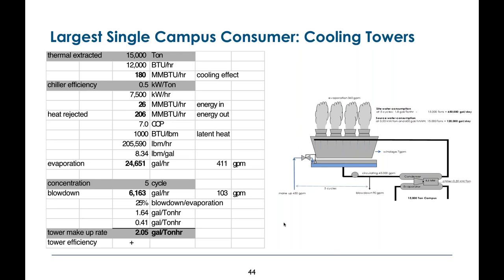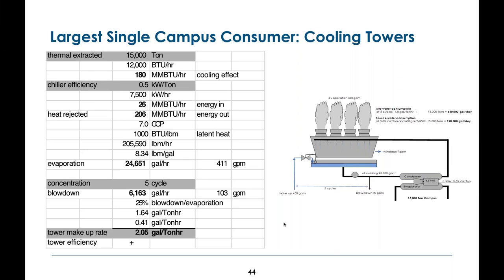The other factor in a cooling tower is the cycles of concentration. That's the amount of water you've got to continuously draw off to keep the concentration of solids in the makeup water from building up to a level where it affects the efficiency of the chiller tubes. This is really the core of the energy-water nexus of a chiller plant: if you aren't spending enough water to keep the purity up, you scale the tubes, so you're trading water on one side against energy efficiency on the chiller on the other.